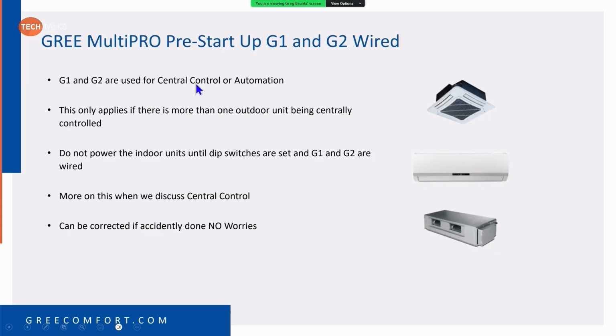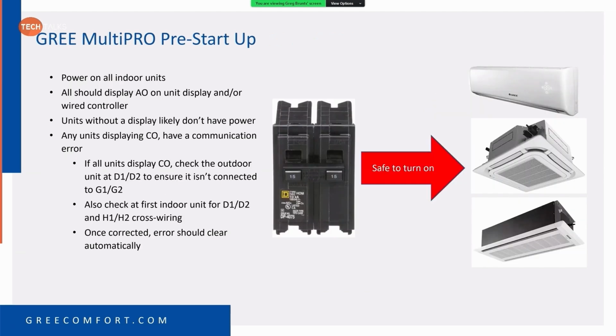G1 and G2 are used for central control or automation, just kind of an FYI. So anytime you're going to have a job where you're going to have more than one outdoor unit and you're going to use central control or cool automation, pre-startup, power all the indoor units on, also display AO on the unit and or wired controller.